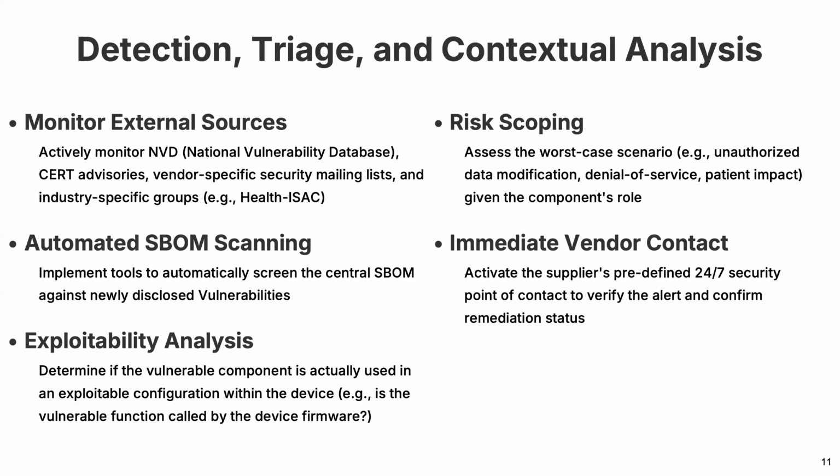The only thing I would add, this isn't like a nice to have best practice. This is the expectation of the FDA, right? So the regulator expects that you are managing your software bill of material against some sort of vulnerability, and you have a process in place to assess those and demonstrate why you do or do not need to take action.